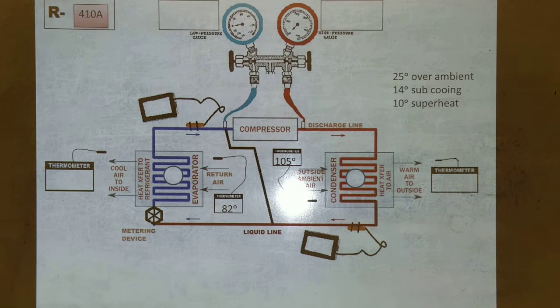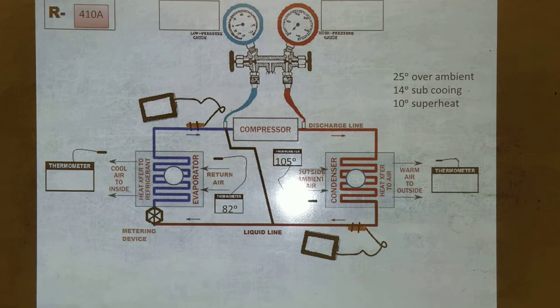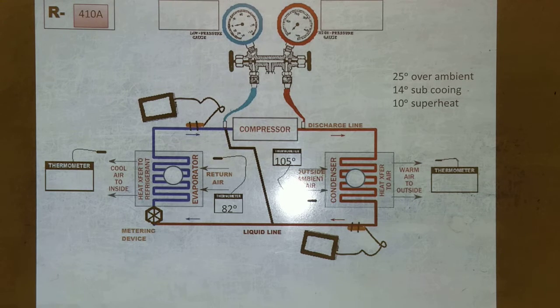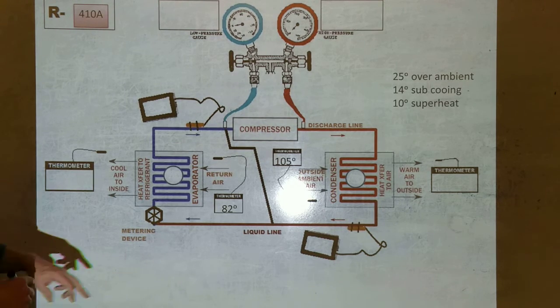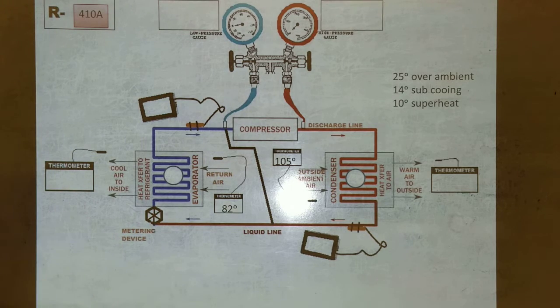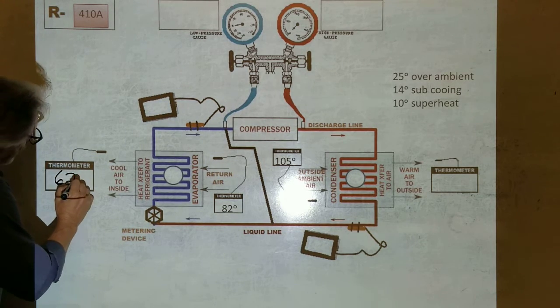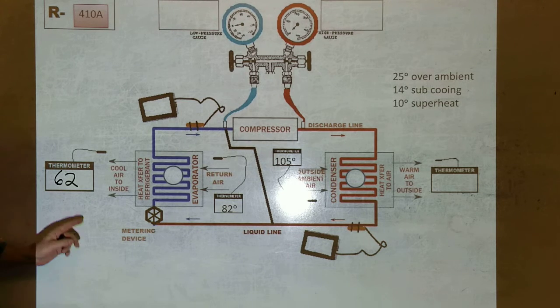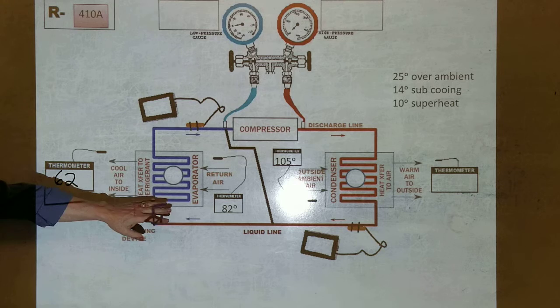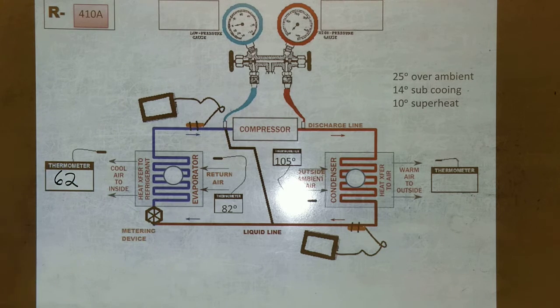Okay, so here's what you're gonna do. 20-degree difference. We got 82 degrees in the building, right? So we're looking for 62. If we get 62, yeah, it's good, because you got 20 degrees. That unit is doing what the manufacturer designed it to do. It's supposed to do that. So a lot of times, suppose you're getting something less.